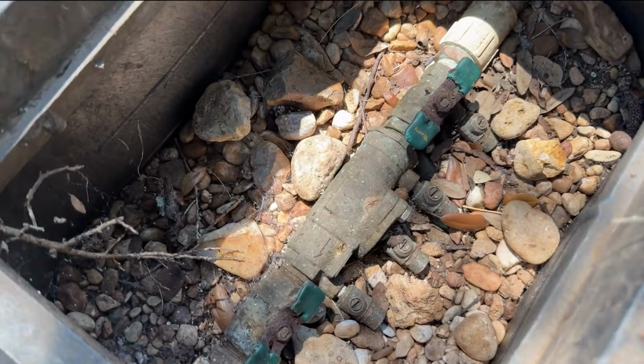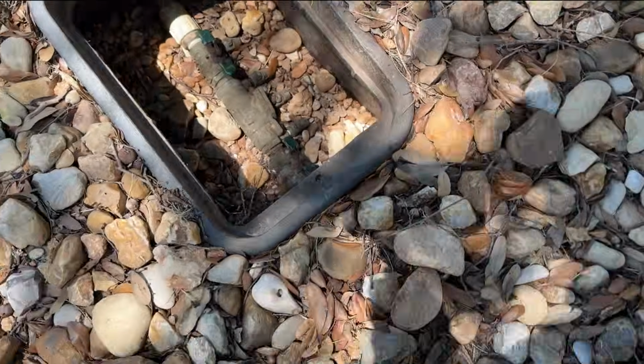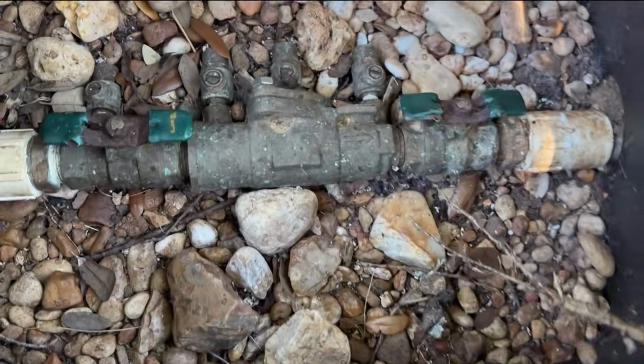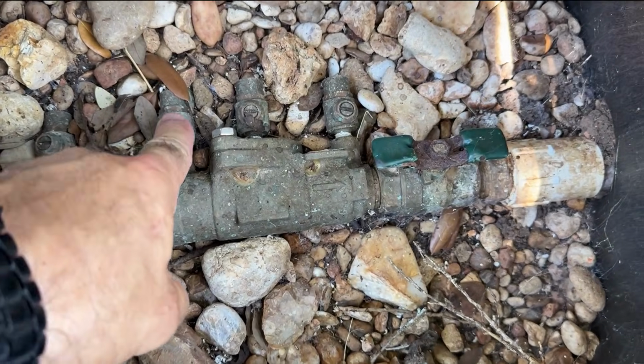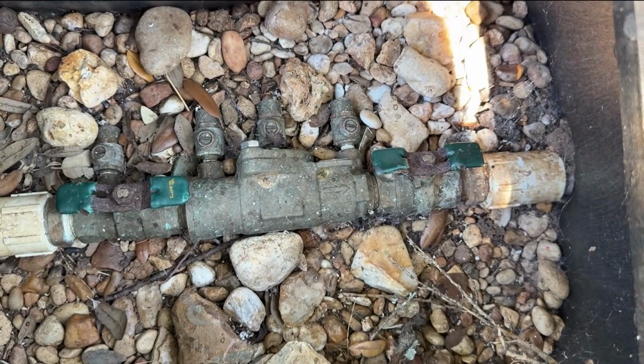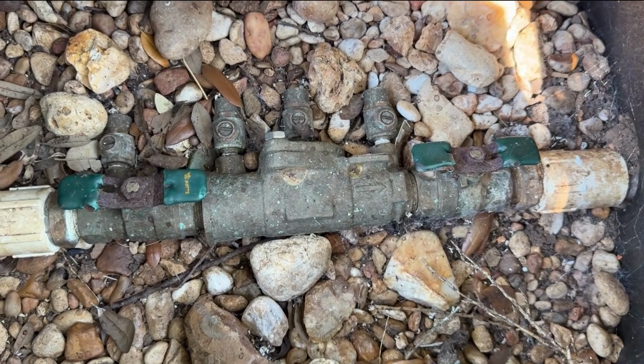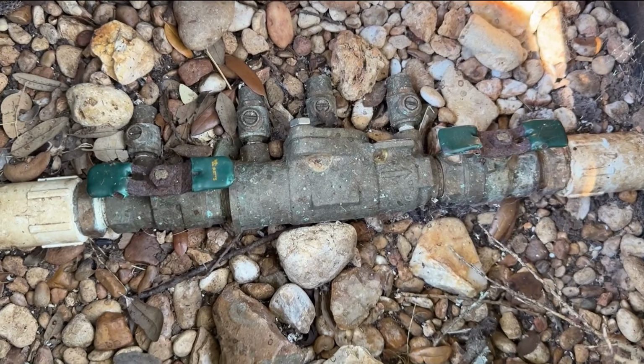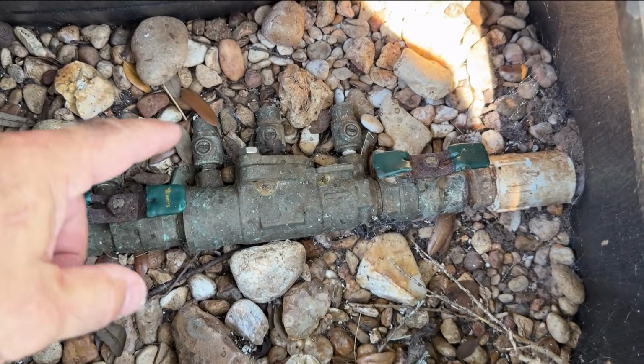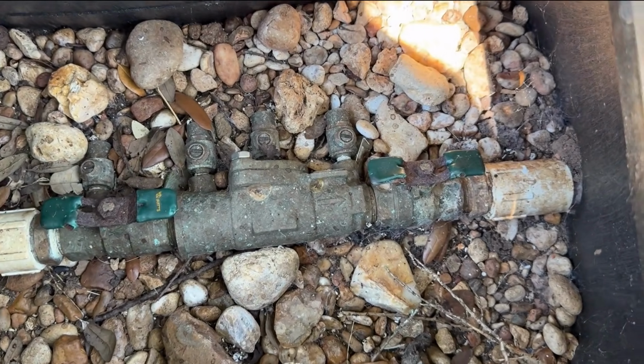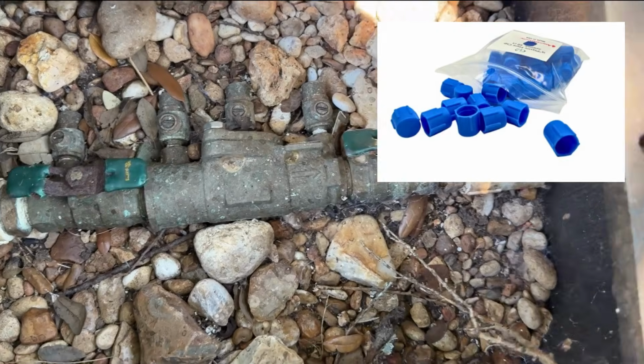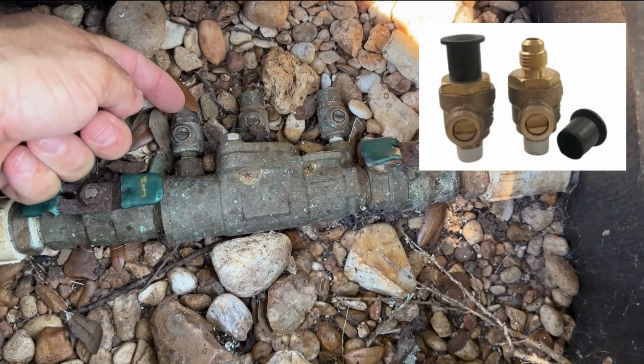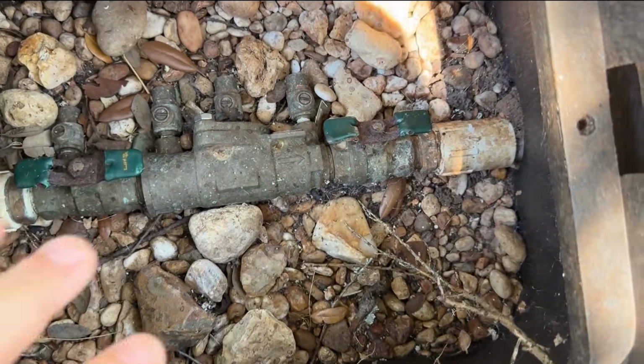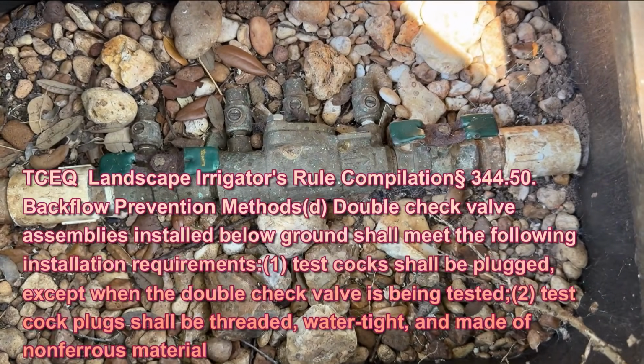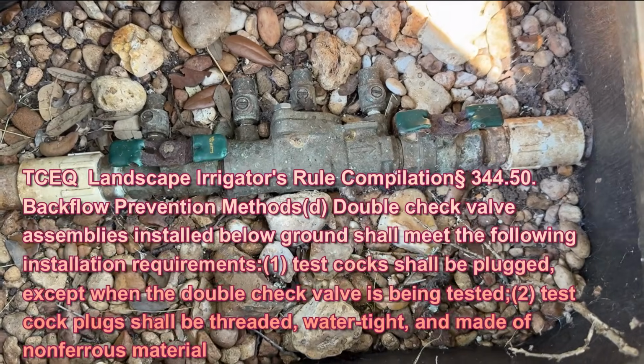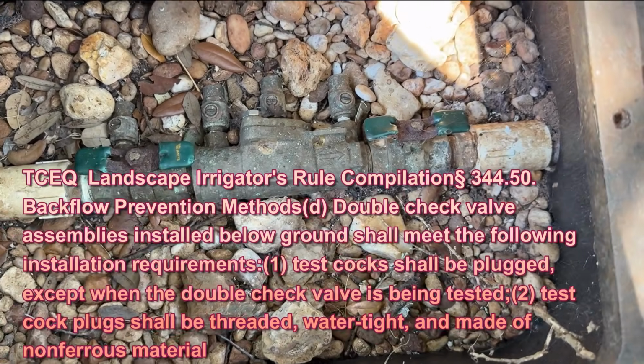One of the next things we're looking at, and that we actually write as a deficiency on our report, are these guys right here. So these are referred to as test cocks, and those allow you to bleed the system out, whether you're winterizing it, shutting it down. But those test cocks have little non-ferrous caps that are required to be at the ends of those to prevent dirt and debris from getting into those openings. And this one right here doesn't have those test cock caps, so we're going to write those up and note that they're missing on this backflow preventer.